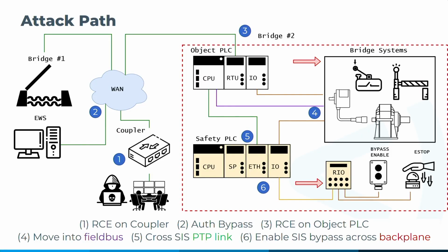Now, what happens is that from the SCADA interface, they talk to a coupler device, and this has a very limited interface that doesn't allow you to talk to the bridges directly. You just are able to manipulate some values that are exposed on part of this coupler that say open or close this particular bridge. And the coupler then talks to the individual bridges.